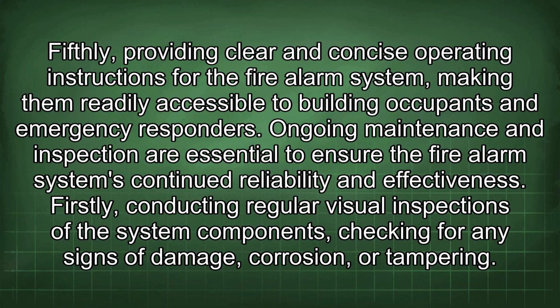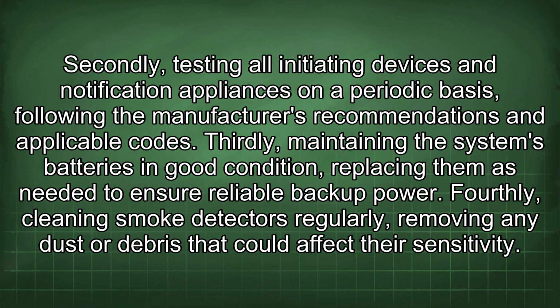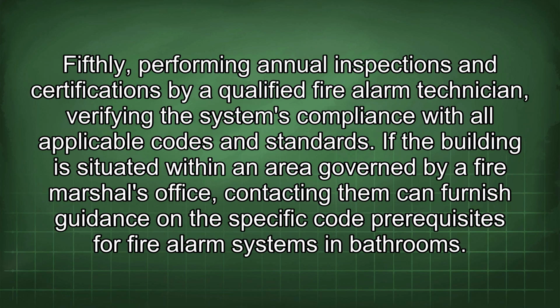Ongoing maintenance and inspection are essential to ensure the fire alarm system's continued reliability and effectiveness. Firstly, conducting regular visual inspections of the system components, checking for any signs of damage, corrosion, or tampering. Secondly, testing all initiating devices and notification appliances on a periodic basis, following the manufacturer's recommendations and applicable codes. Thirdly, maintaining the system's batteries in good condition, replacing them as needed to ensure reliable backup power. Fourthly, cleaning smoke detectors regularly, removing any dust or debris that could affect their sensitivity. Fifthly, performing annual inspections and certifications by a qualified fire alarm technician, verifying the system's compliance with all applicable codes and standards.